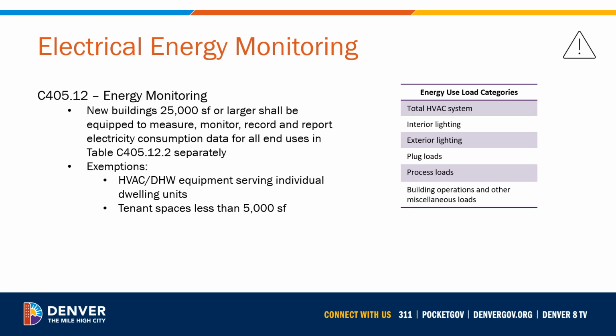A new mandatory requirement for electrical energy monitoring has been added to the 2022 Denver Energy Code. This requirement states that electrical consumption data of various energy use load categories must be measured, monitored, recorded, and reported separately for new buildings with a gross conditioned floor area of 25,000 square feet and greater.